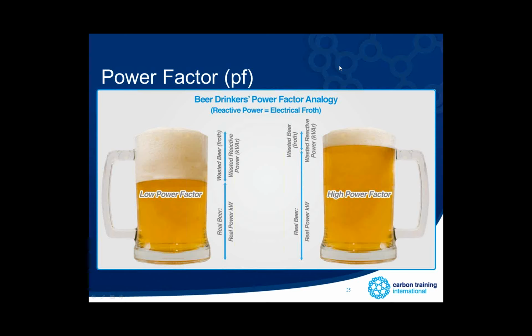So power factor correction actually says to that 100 kilowatt motor, okay, here's what you're doing to the network, I'm going to correct that and actually make sure that the 100 kilowatt power demand from the motor is recognised by the network as a 100 kVA load. And in that case, it would save us that $280 a month.